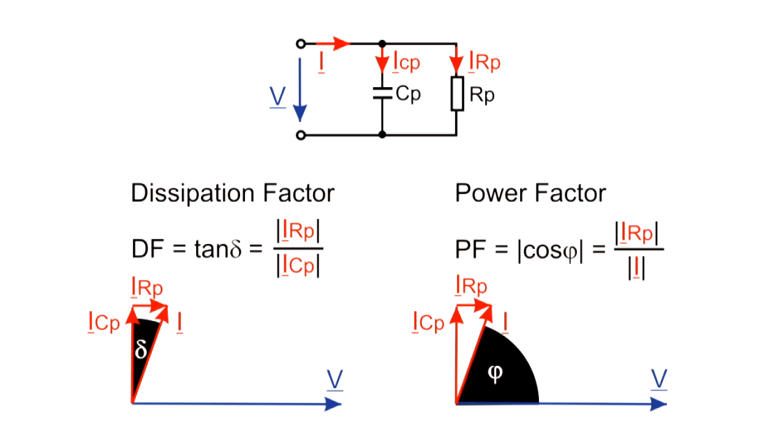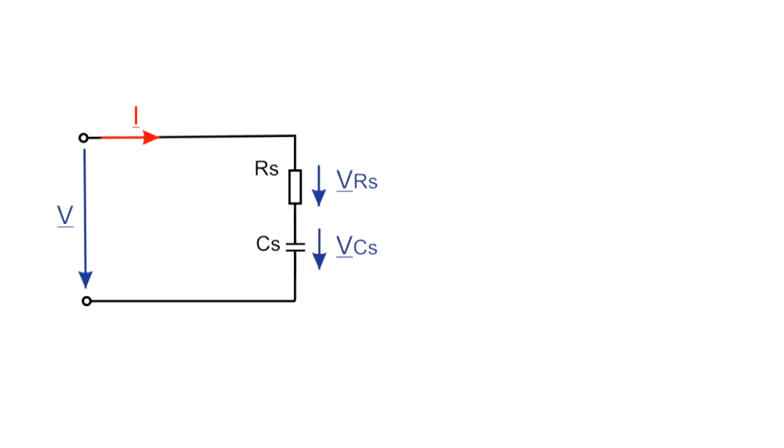Conductive losses which result in DC leakage currents can best be represented with a parallel equivalent circuit. Polarization losses, which may result from AC voltages, can be represented by an equivalent circuit consisting of an ideal capacitor with a resistor in series.